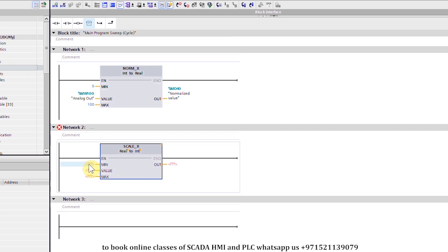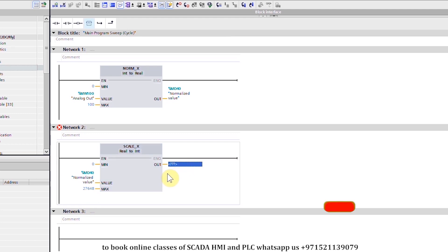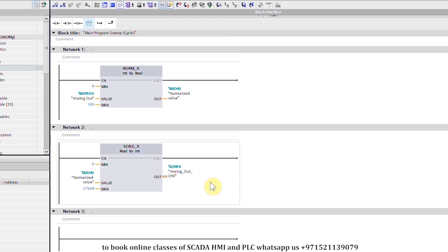In the minimum we will insert zero. In the value input we will insert the same normalized value MD40, and in the maximum we will insert 27648. In the output we will enter the same output word QW96 for analog channel zero. The SCALE_X function will take the normalized value, scale it from zero to 27648, and output the result onto QW96 for output channel zero, which will generate zero to 10 volts.